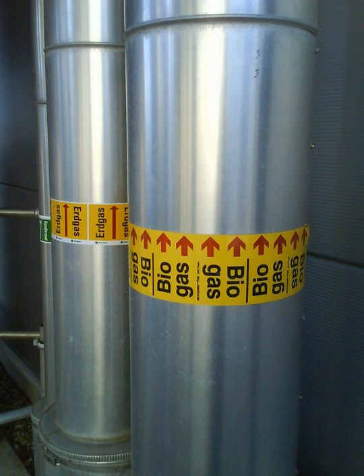Gas to be upgraded enters each vessel, is compressed to a high pressure whereby the gas to be removed is adsorbed onto the surface of the adsorbent, and is then decompressed, allowing the methane to leave. The adsorbent is then regenerated. For oxygen, molecular sieve is used, for nitrogen a zeolite, for carbon dioxide and water a zeolite or activated carbon.